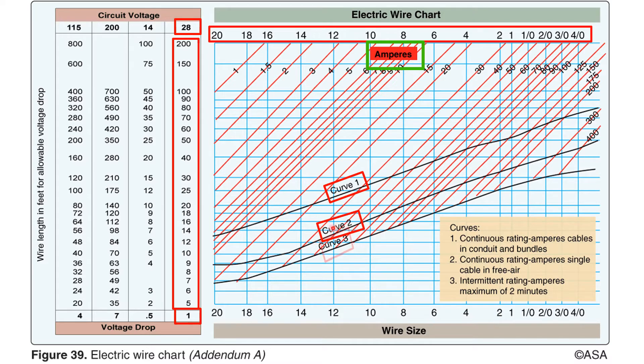Curve 3 represents intermittent circuits running for a maximum of 2 minutes. Examples of these types of circuits are flap motor circuits, starter and landing gear circuits. Because these circuits do not accumulate heat over longer periods of time, they may utilize a smaller gauge wire for a given current flow.